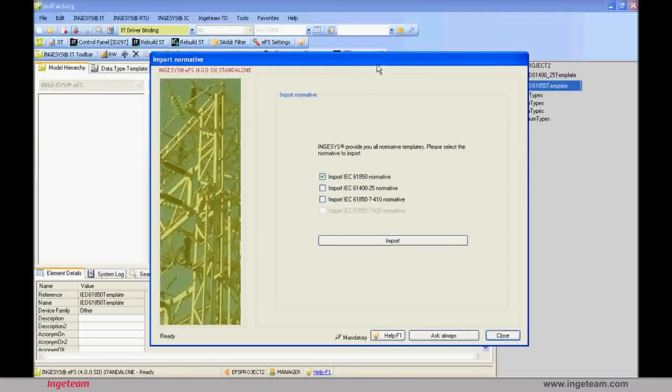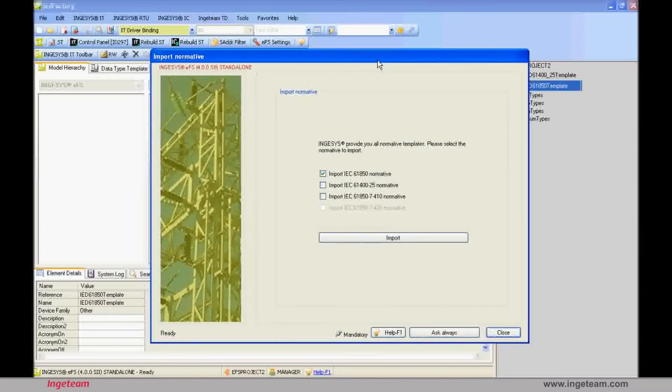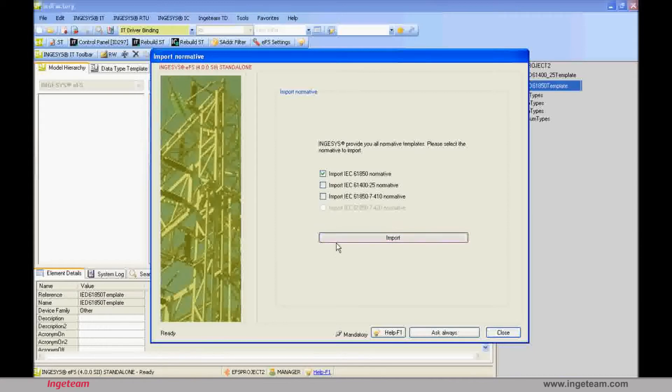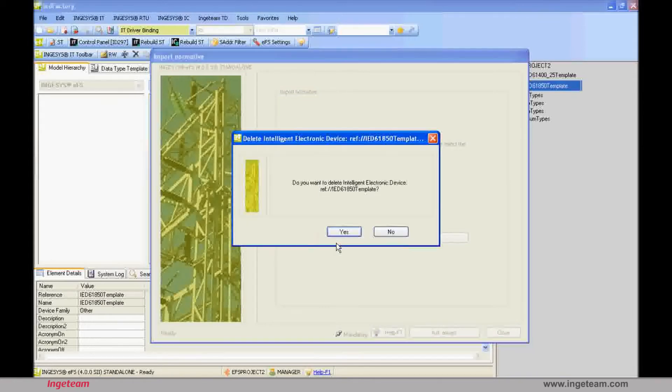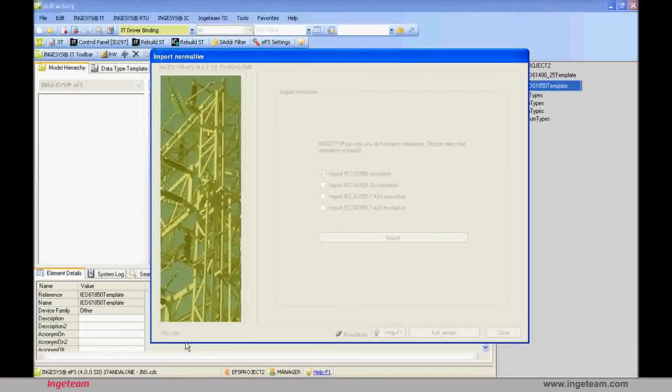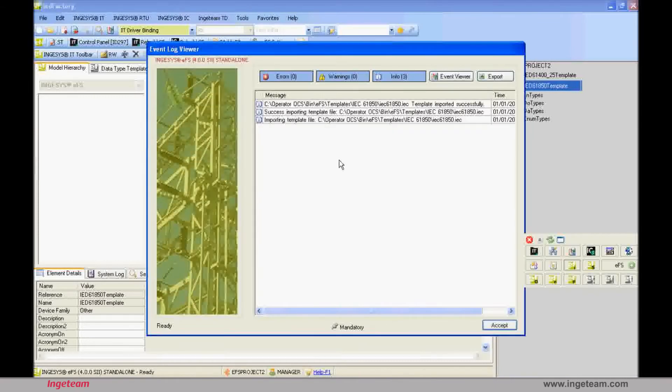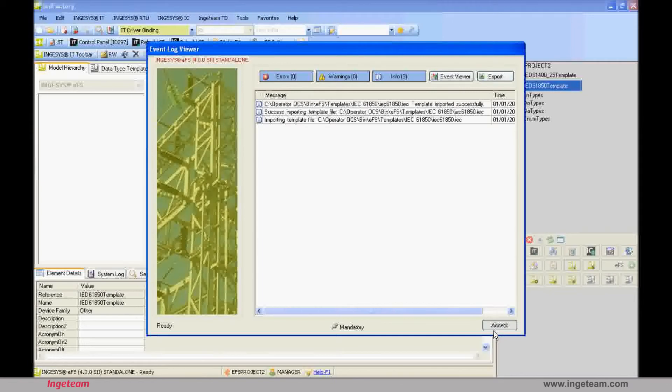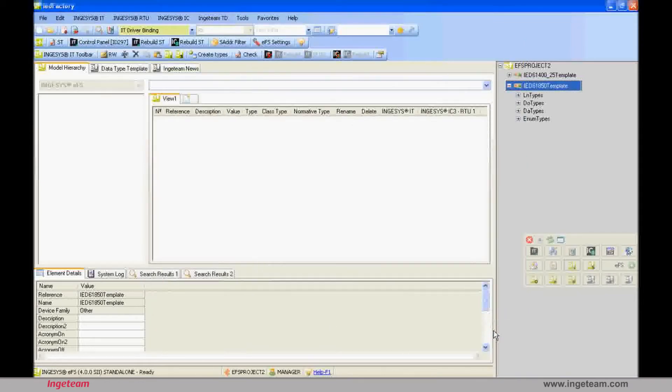To start, choose the IEC 61850 standard. When you select it, the tool will ask whether you want to overwrite the standard that was in the project, deleting the previous one. In this step, the different types of information are imported from the lower levels such as data attributes to more complex information models such as common data class, ending with high level functions or logical nodes. At the end, a dialog box will be shown indicating the result of the import process. There have been no errors or warning messages. There are only informative messages indicating that the process has finished correctly.